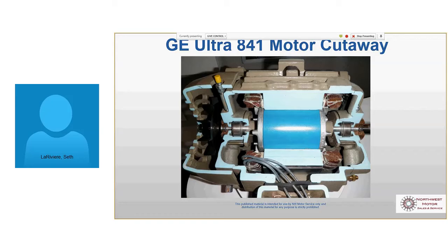So we basically flip these seals around. We also either pin or throw a weld bead around the rotor to the shaft so that the rotor doesn't slide on the shaft. Those are basically the 3 things. You've got to repath the grease, pin the rotor to the shaft, and just let us know. If you're applying these over 75 horsepower, we will have to make those modifications. There's nothing under 75? Yeah, under 75 we're good.